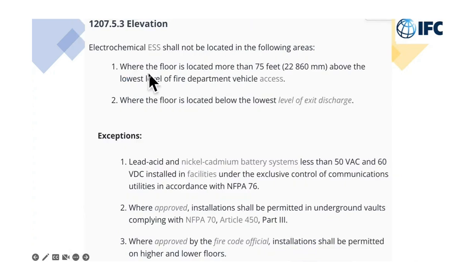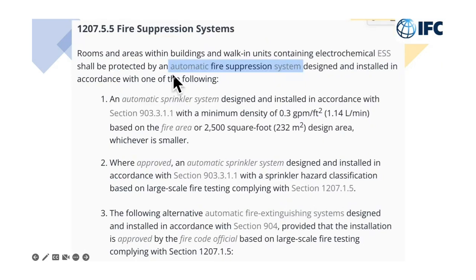There's elevation. This has to do with ESS not located in the following areas: where the floor is located more than 75 feet above the lowest level of fire department vehicle access. I believe that has to do with your fire truck ladders and how high they can get somebody, 75 feet, and where the floor is located below the level of exit. And then there are some exceptions, like if you are friends with the fire code official, and lead acid batteries and things like that. And then we, of course, have automatic fire suppression systems, such as sprinklers, things like that, fire extinguishing systems.